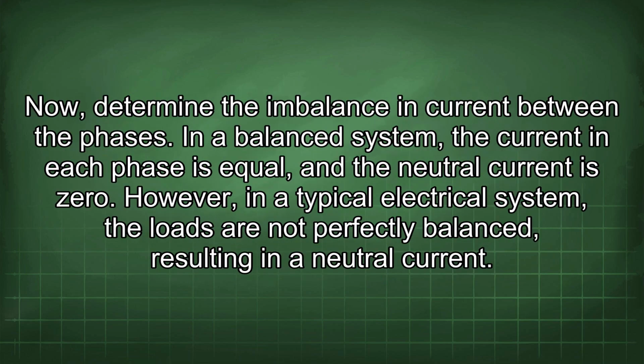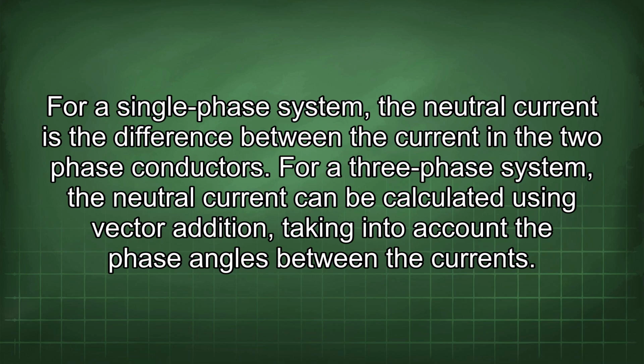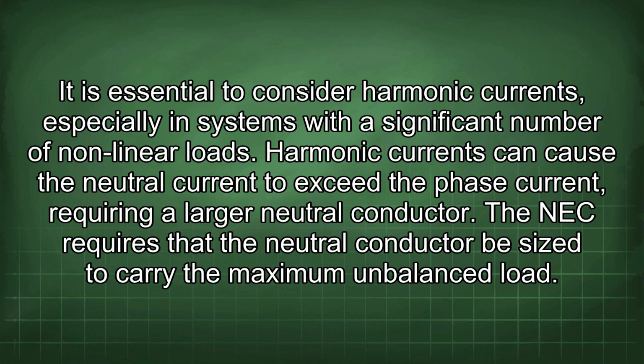Now, determine the imbalance in current between the phases. In a balanced system, the current in each phase is equal, and the neutral current is 0. However, in a typical electrical system, the loads are not perfectly balanced, resulting in a neutral current. For a single-phase system, the neutral current is the difference between the currents in the 2 phase conductors. For a 3-phase system, the neutral current can be calculated using vector addition, taking into account the phase angles between the currents. It is essential to consider harmonic currents, especially in systems with a significant number of nonlinear loads.